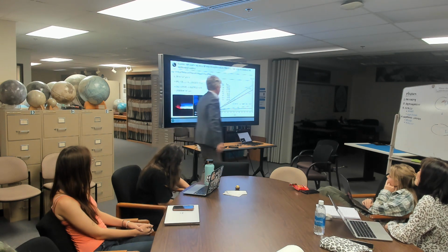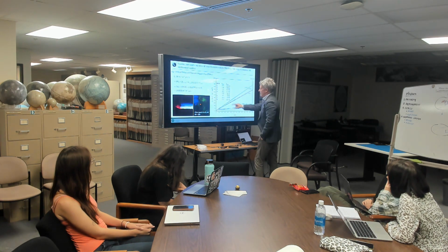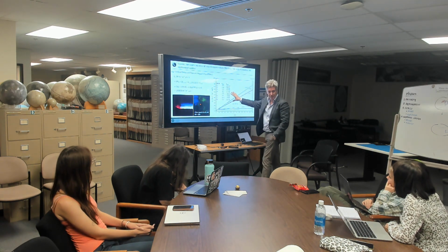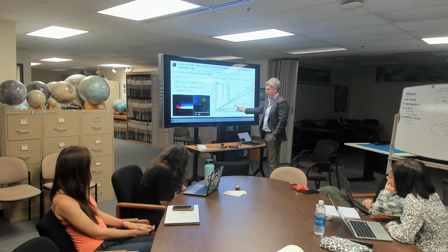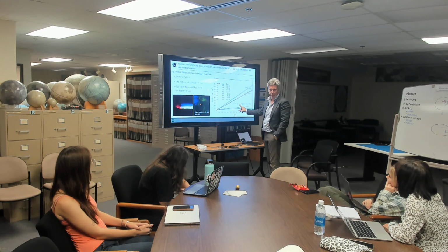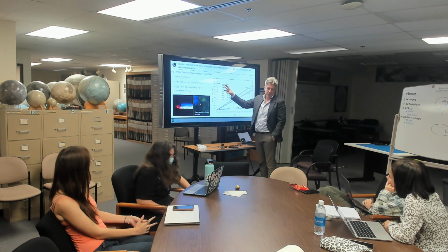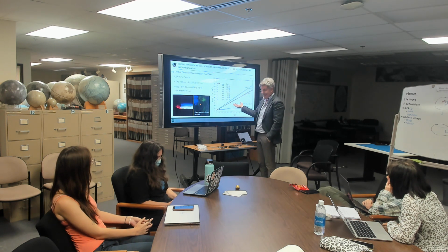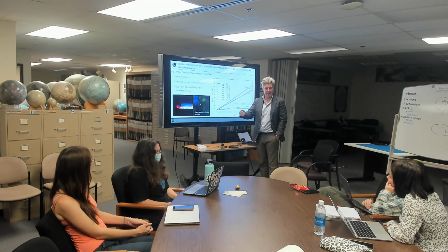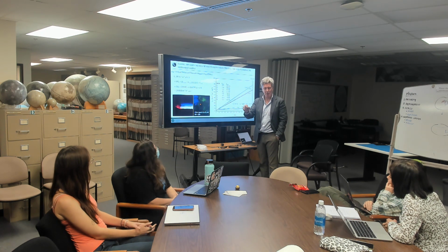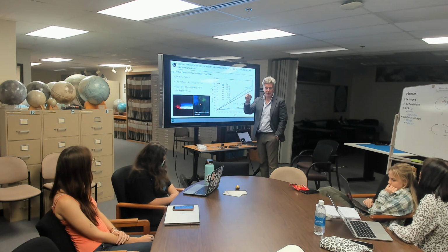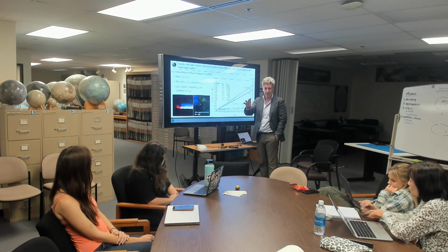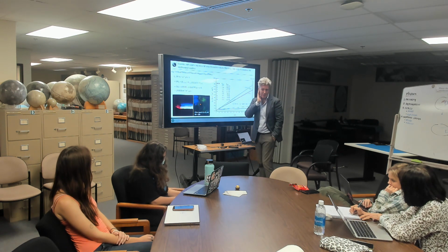I've just plotted these things up for different DNs against radiances for all these different bands. And you see it's just the equation of a straight line, y equals mx plus c. An instrument that isn't calibrated is not an instrument. If all I get from it is DN, and I don't know how DN translates into spectral radiance, or how a change in DN from 255 to 254 translates into real numbers like spectral radiance, then I can't do any science with that instrument at all.